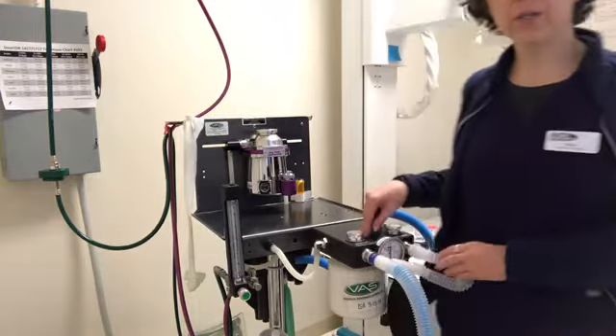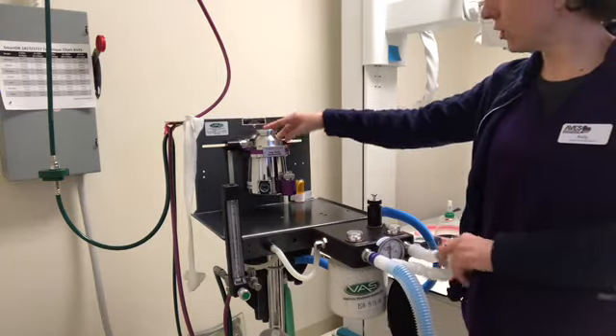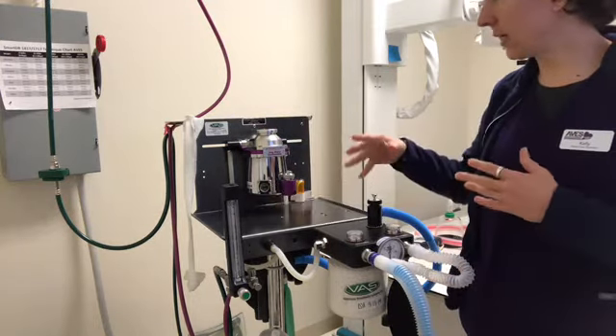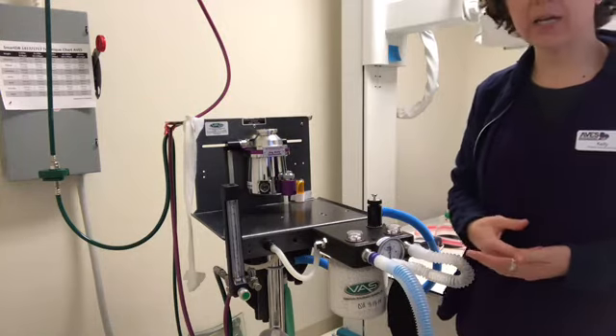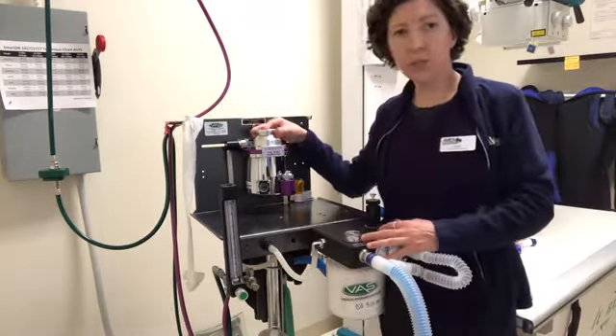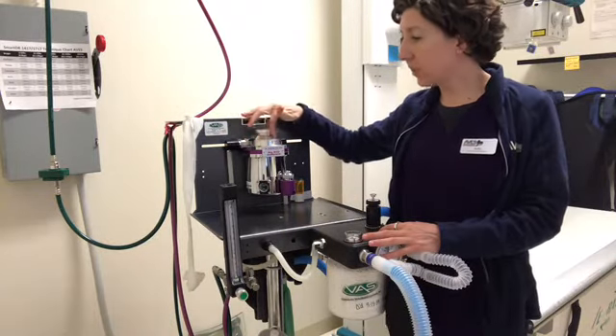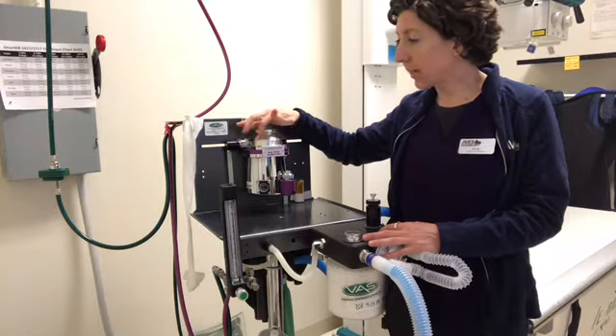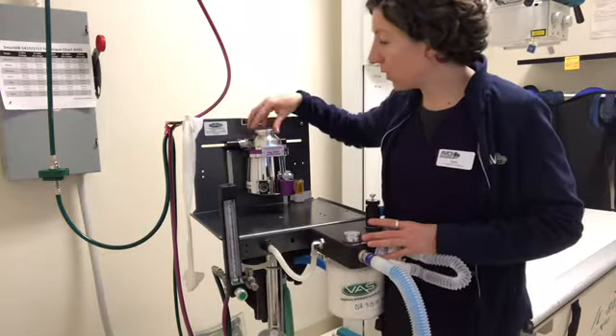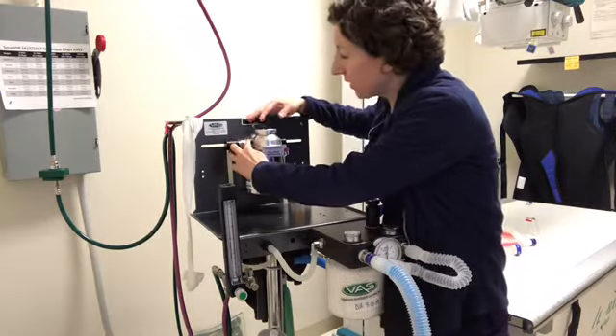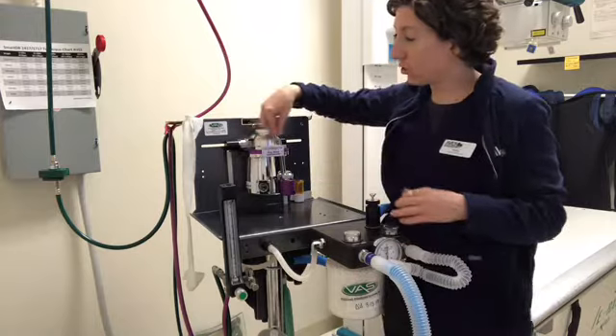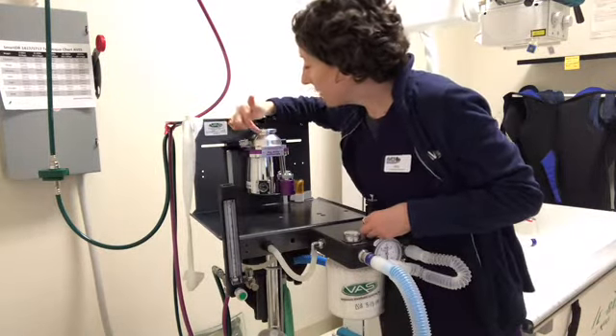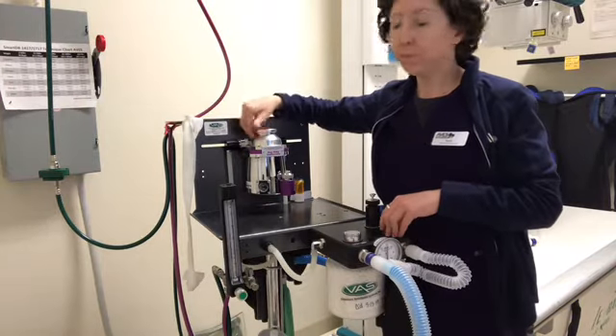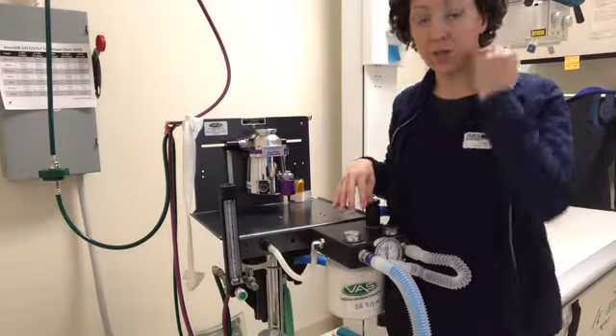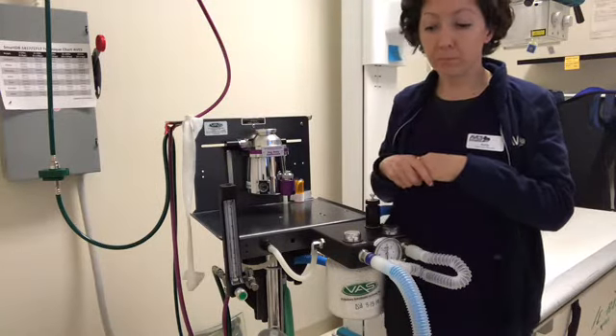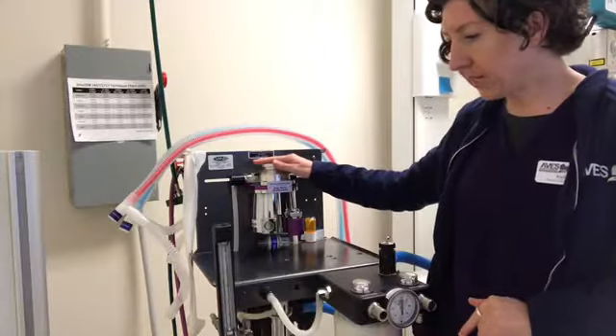So the function of the vaporizer is to convert liquid anesthetic to a gas state, so then the patient can inhale it. And the reason it's called a precision vaporizer is because it allows us to choose exactly what rate we want. To turn this on, you would press the little black button here on the left and then turn it to your desired rate. It's 0.5, 1, 1.5, 2, and you can even go in between those dashes, so you can really control the rate of flow.